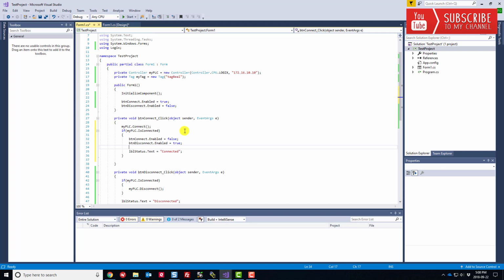I mean, this is going to set up a continuous polling of the tag, which may or may not be efficient depending on the type of value that you're reading and what you're doing. So, if we're reading an analog value that we want to tie to a trend, then we want to sample that at some very consistent rate. But again, we're polling it. There are other ways that we can sample tags.